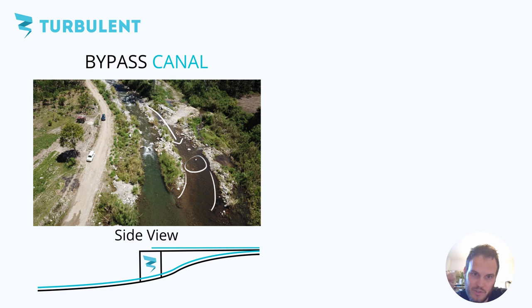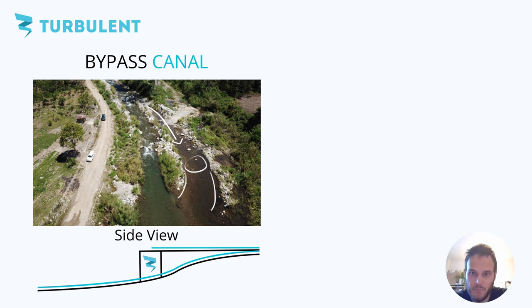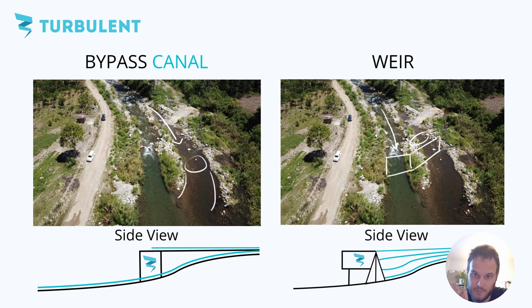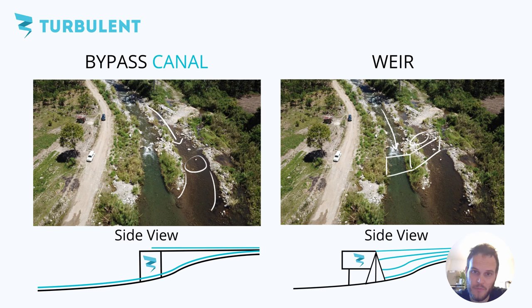Talking about civil works there are two ways that you can extract energy from a river with a very low gradient. Either you can make a bypass canal where you put the water in a side river with a lower gradient than the main river and you basically keep the water at a higher level until it reaches your turbine and then you drop it back down to the river. Or you can build a weir in the main river and immediately after that you put your turbine. Now usually we advise you to make a bypass canal not only because it's often cheaper to make than weir of the whole width of the river but it's also more ecologically sound.